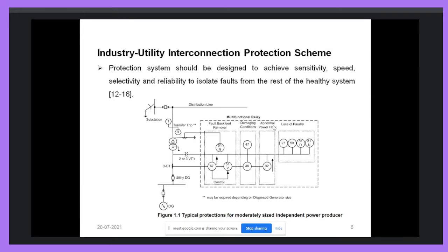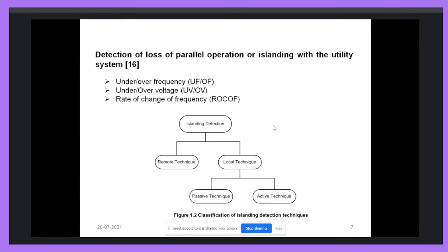So we have to sense the parameters of the system, and on the basis of the threshold values which we have decided, we have to disconnect the system whenever there is an abnormal operating condition in the grid. The detection of loss of parallel operation, or integration with the grid, that is islanding, can be classified as remote technique and local technique. The local technique is further classified as passive technique and active technique. Basically, the techniques utilized in an industrial system are under/over frequency, under/over voltage, and rate of change of frequency. These are the three protection schemes basically utilized for islanding detection in industrial systems.